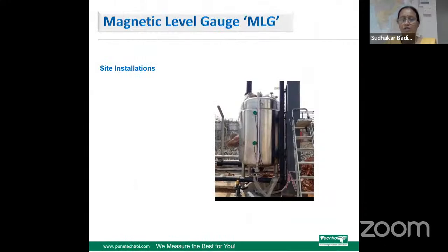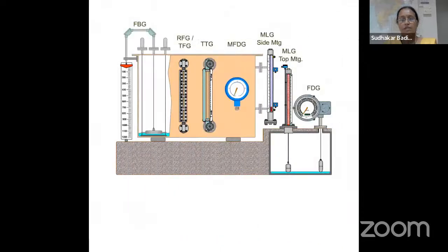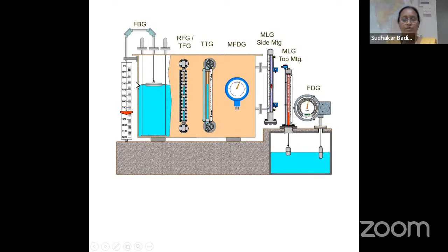This is the site installation, how this gauge is mounted on the tank. You can see it from the side of the tank. So this is the animation of the installation of the various level gauges. The first one is a float and board gauge. When this float moves according to the liquid level, this pointer also moves on the scale, and you can see the liquid level on the gauge. And in RFG, TFG, or TTG, you can see the liquid level through the gauge glass.